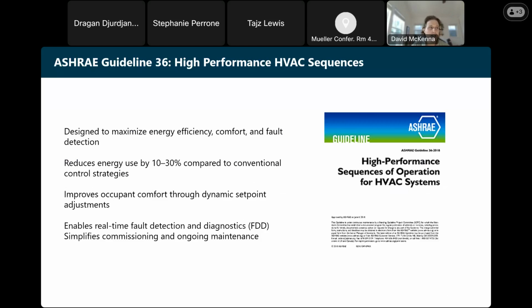So ASHRAE Guideline 36 is really a treasure trove of information for us. It enables us as design engineers to go in there and, in some instances, it's not always this easy, but we can copy and paste a lot of these control strategies and sequences directly onto our drawings. What we do obviously is specify the equipment, and then it's really important to convey how we expect that equipment to run. An increasing part of our job as engineers is getting involved in the control systems and the controls infrastructure side of things. ASHRAE Guideline 36 really helps us understand how best to optimize that equipment's operation.